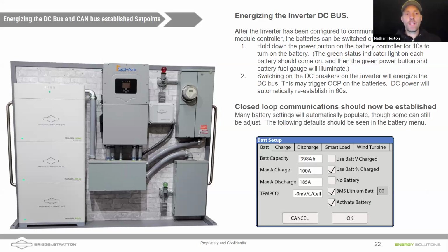If the programming has been done successfully and it's communicating with the batteries, you should see the battery capacity immediately show up under battery setup. So for a stack of 3 batteries, it'd be 398 amp hours. It's a 20 kilowatt hour stack that you see in that picture. And then the default for the Sol-Ark, it has some global charge limits that are there. I'll talk about that on the next slide.